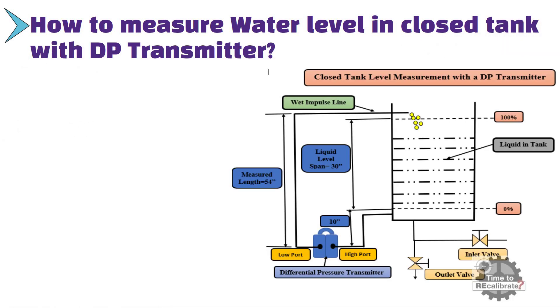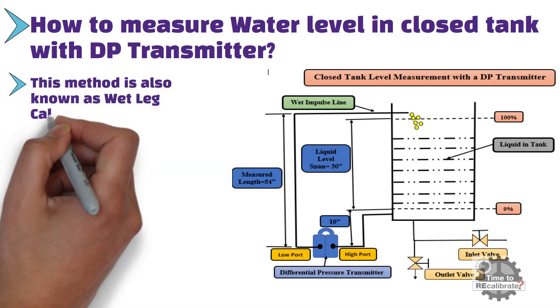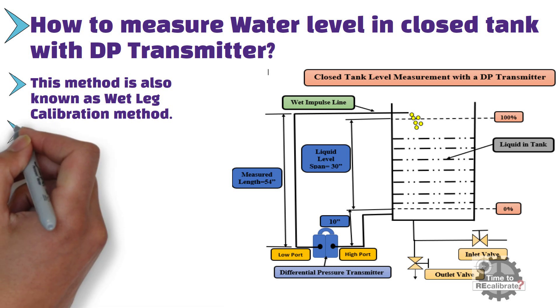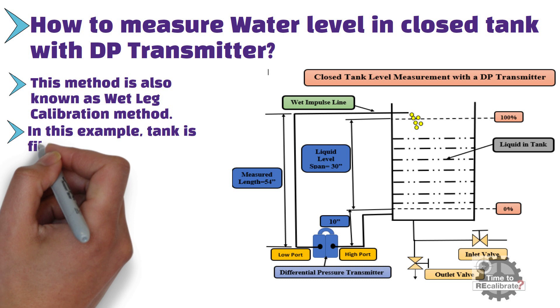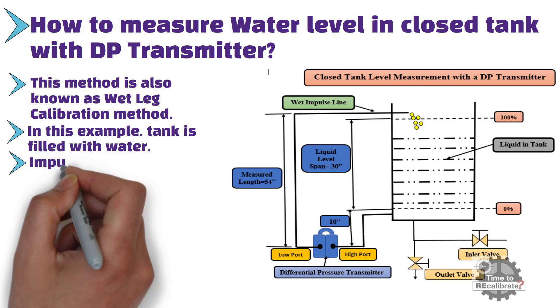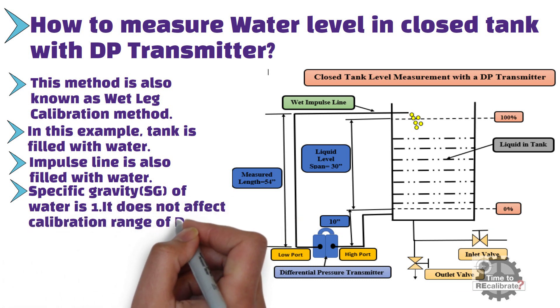How to measure water level in a closed tank with a Differential Pressure Transmitter? This method of level measurement is also known as the wet leg calibration method. The specific gravity of process fluids plays a crucial role in the calculation of the calibration range for a DP transmitter. In this example, let's assume the tank is filled with water and the impulse line is also filled with water. Since the specific gravity of water is 1, it does not affect the calibration range.